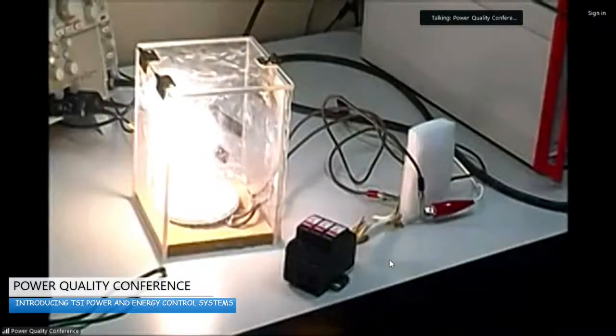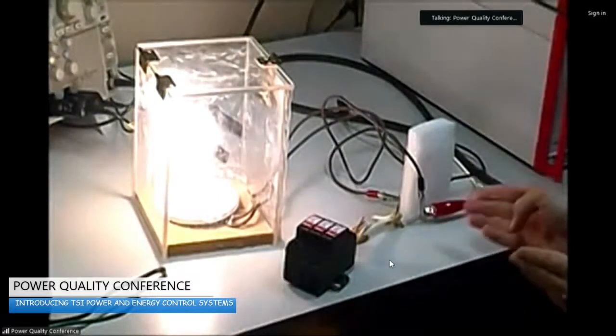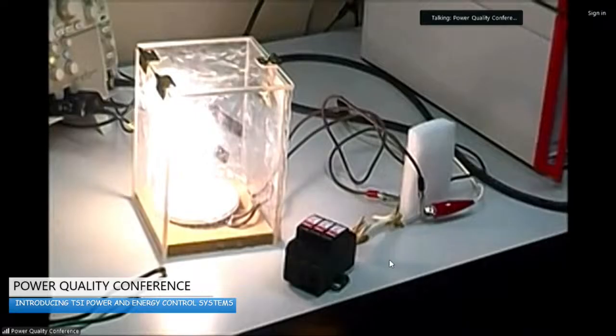Today we're going to run a 6,000 volt, 3,000 amp surge test on this light bulb circuit and a very popular internationally known surge suppressor, Phoenix Contact, to see what type of positive benefit it'll have on protecting electrical equipment, but also consider the electronic equipment downstream. The suppressor is installed in parallel to the lighting circuit.